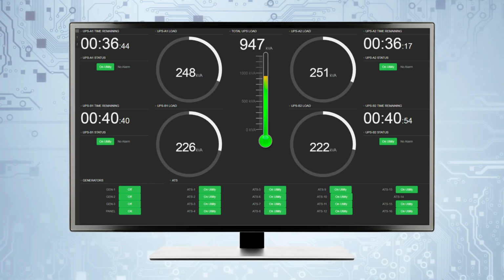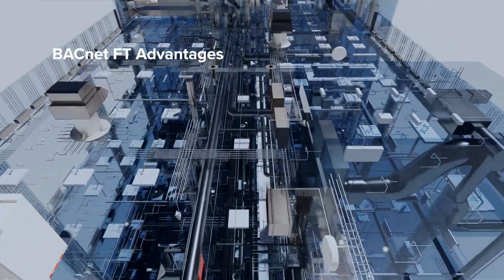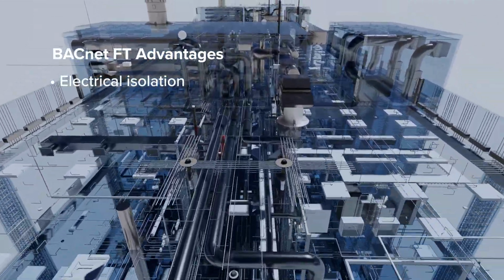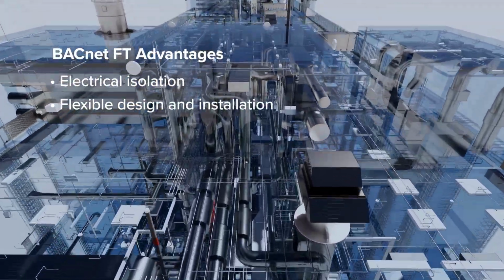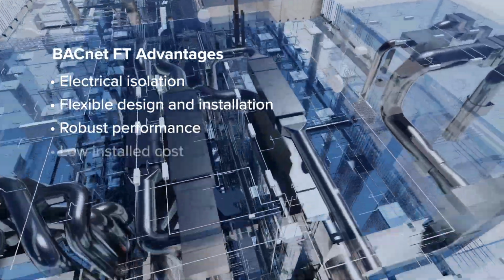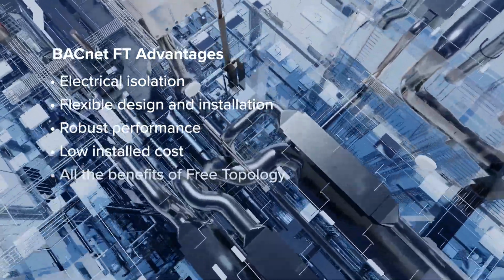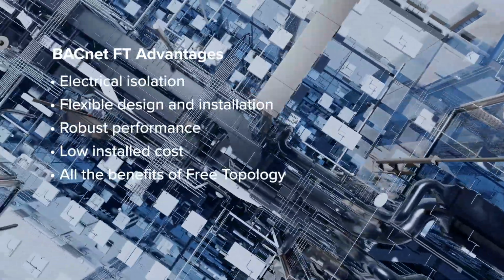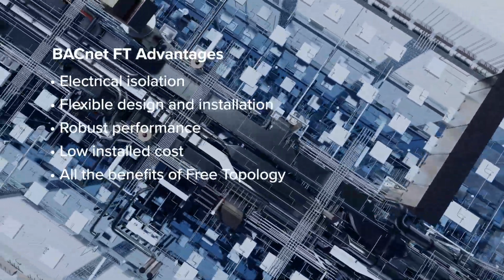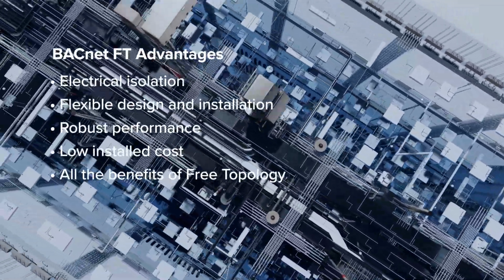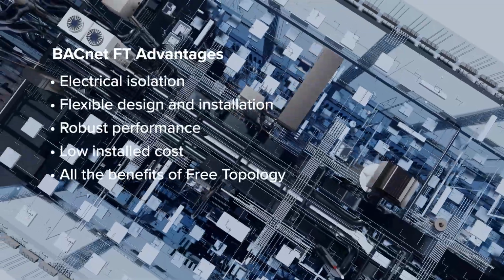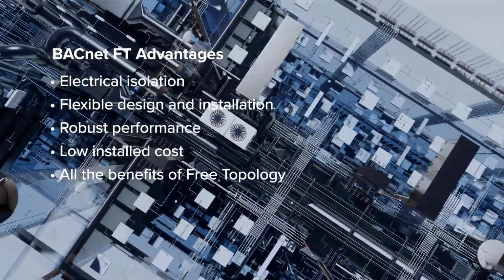From an electrical perspective, BACnet FT is more reliable because it is always isolated and it can be laid out in a free topology basis. It doesn't have to be a bus network with terminations at the ends. This gives it great advantages over protocols like BACnet MSTP, which is sensitive to grounding issues, MAC address collisions, line termination issues, and latency problems.